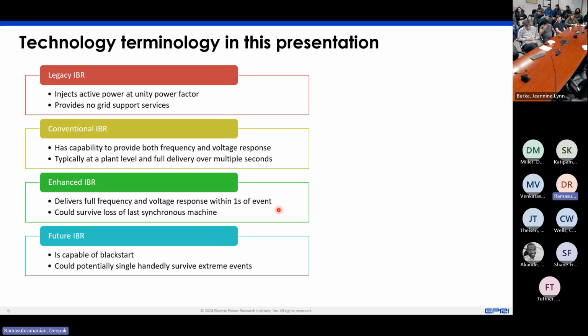What we've seen is that, as a group, they can survive the loss of the last synchronous machine. So maybe one inverter by itself cannot survive that loss, but as a group, three, four, five inverters together can survive it—meaning they're cooperatively able to improve the stability of the network. That's a drastic improvement over the two categories above, where even cooperatively, they couldn't survive the loss of the last synchronous machine.